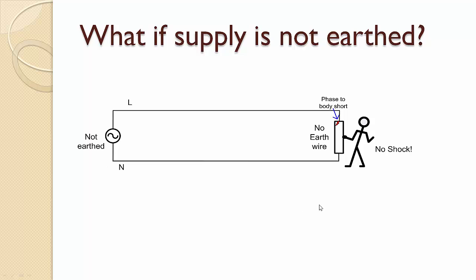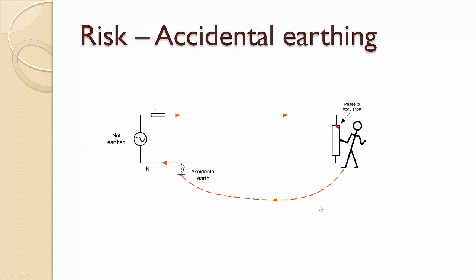But still, why do we earth the power supply if it only increases the chance of shock by providing a complete path for fault current? The answer is: suppose one of the wires is accidentally grounded—grounded means the live conductor touches the ground or some grounded body—and suppose the other wire is shorted to the body of equipment. What will happen? A person handling this equipment will get a nasty shock, especially if this system doesn't have an earth wire to bypass this current to the earth.